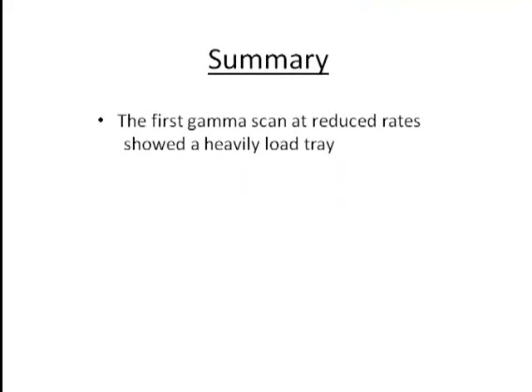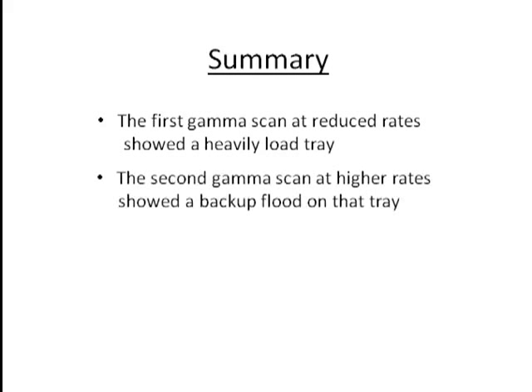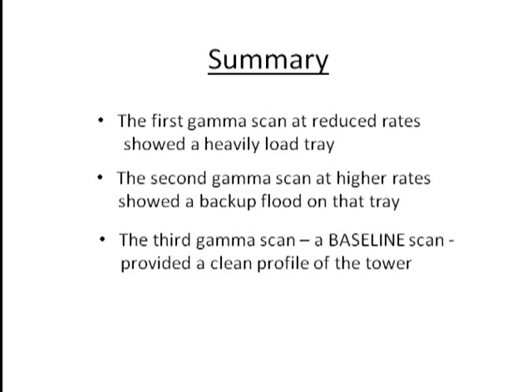In summary, the first gamma scan at reduced rates showed a heavily loaded tray. The second scan showed a backup flood on that tray, and the third gamma scan, a baseline scan, provided a clean profile of the tower.